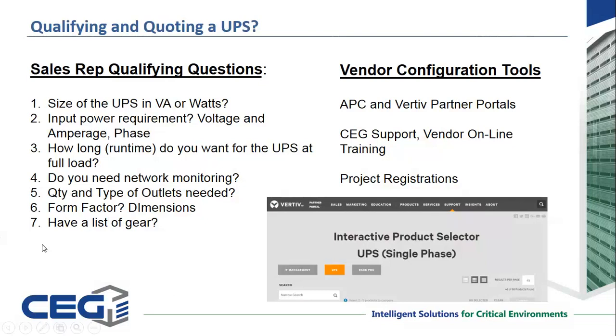Do you need network monitoring? The lower end units rule that out; some of the line interactive products do include the ability to have a network card like you saw, and most all of the double conversion online units do as well. That either comes included, like in some of the Liebert offerings, the higher end ones, the higher kVAs, they'll include the network card as part of the SKU now. They'll include the rack mount rails as part of the part number and part of the price. That used to be kind of separate, so they've bundled that together.